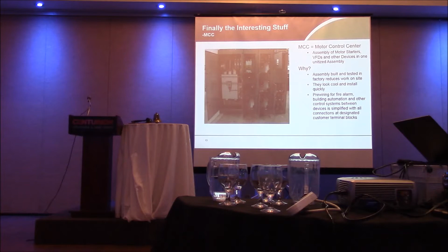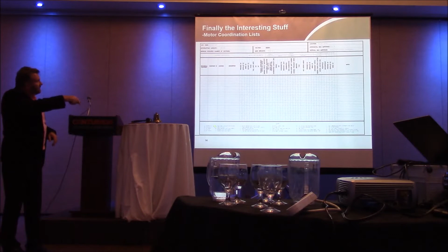This is my motor schedule. This is what I use to specify starters or a motor control center. And I'm not sure how well you can see that, but this big legend down here is a list of all of the options that I can put on a starter or a drive for things like auxiliary contacts, hand-off-auto switches, indicator lights. This is the shopping list of all of the features that we can put on a starter or a drive that will feed into your building automation system so you can get the information you need to properly operate that building.